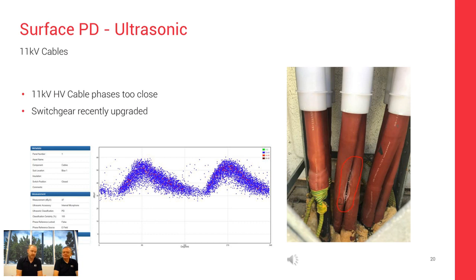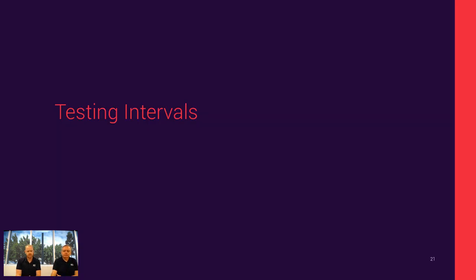We have found that one. That one there was found visually, it was found with our own ears, but the instrument was also able to take a recording of it and help further diagnosis. The algorithm predicted 100% certainty that the sound was being caused by partial discharge as well, so it gives further confidence again, even though we can see it. So that's just another case study.